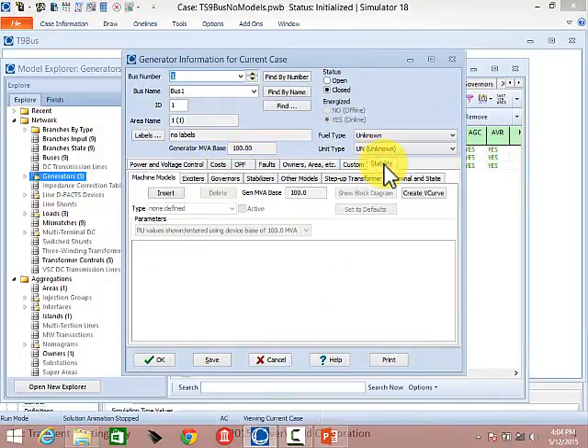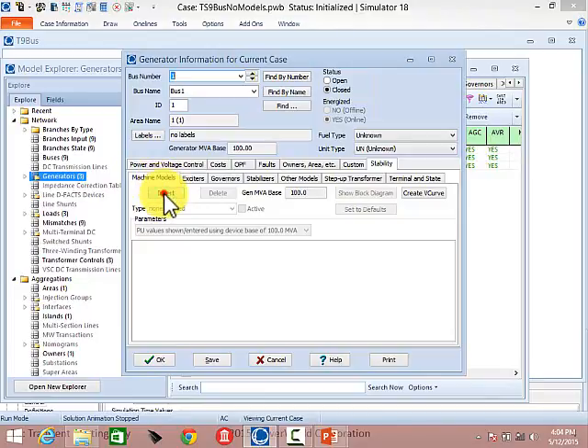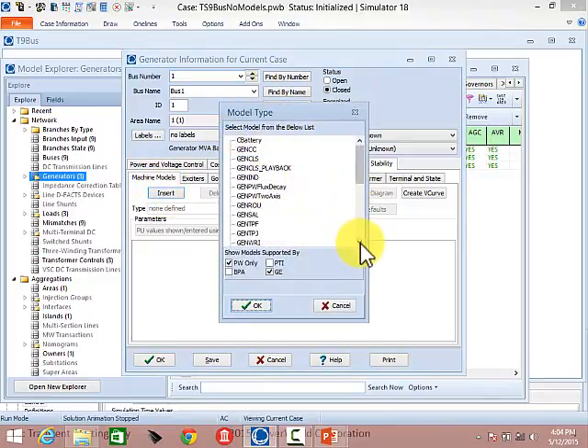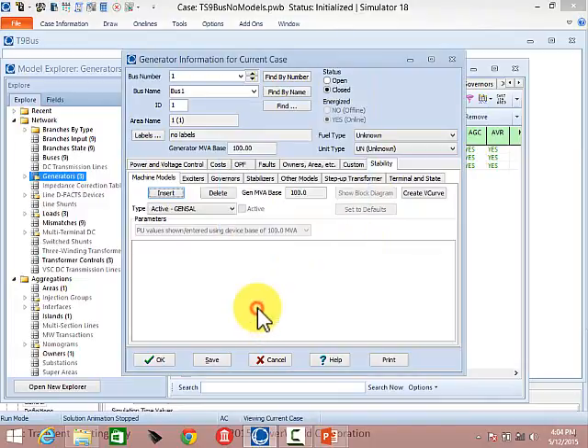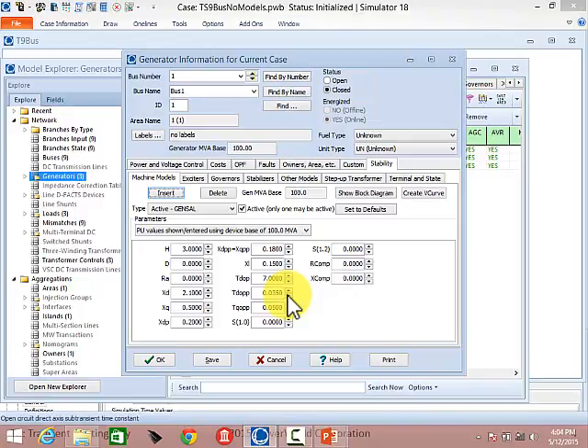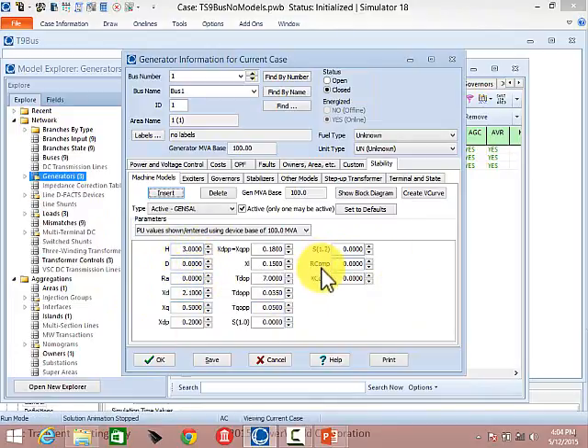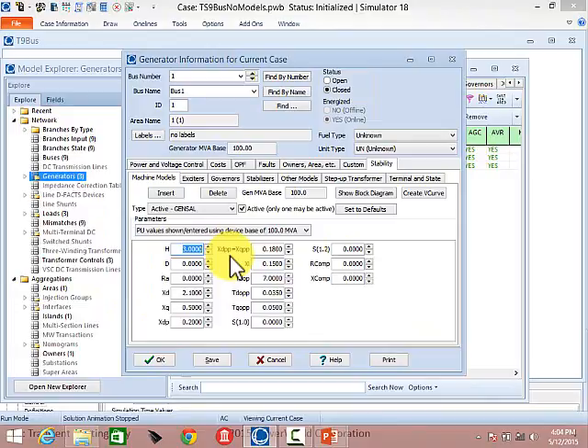Go to the Stability tab and add a machine model. On the Machine Models tab, choose Insert — that brings up all possible machine models. Click on GENSAL and hit OK. For this example, the defaults aren't sufficient; you'll need to enter specific values. Default values appear non-bolded; once you type in a value and leave that field, it becomes bolded, indicating a non-default entry. Whether it's valid is another question, but bolding indicates it has been changed from the default.